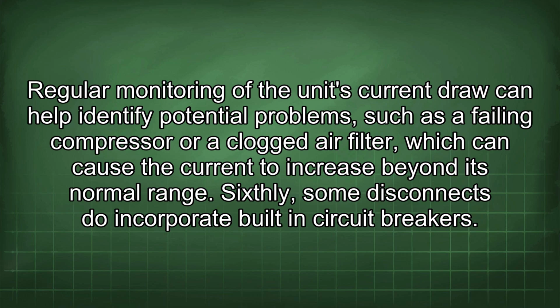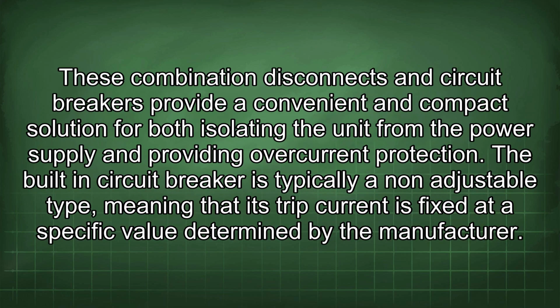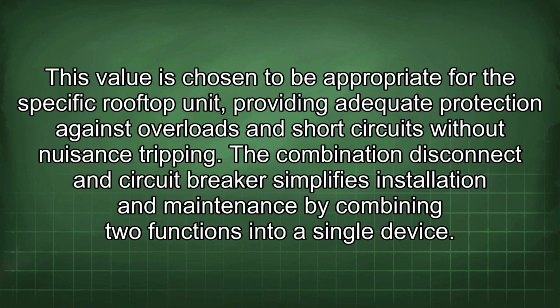Sixthly, some disconnects do incorporate built-in circuit breakers. These combination disconnects and circuit breakers provide a convenient and compact solution for both isolating the unit from the power supply and providing overcurrent protection. The built-in circuit breaker is typically a non-adjustable type, meaning that its trip current is fixed at a specific value determined by the manufacturer. This value is chosen to be appropriate for the specific rooftop unit, providing adequate protection against overloads and short circuits without nuisance tripping.